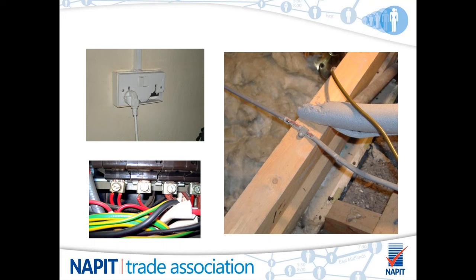Shock could ensue, C1. The picture below that is the inside, obviously, of a distribution board, and it's fairly obvious that the terminal is showing signs of heat damage to the conductors. This is loose and, of course, again, could cause a fire risk.